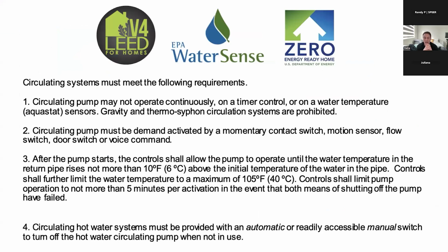In the past, we've seen language as it pertains to hot water recirculation often be pretty ambiguous, right, and open to interpretation. This is not. It says that the circulating pump may not operate continuously on a timer or on water temperature, and gravity or thermosiphon circulation systems are prohibited, and that the pump needs to be demand activated by a momentary contact switch, motion sensor, flow switch, door switch, or voice command. And then after the pump starts, the control shall allow the pump to operate until the water temperature in the return line rises not more than about 10 degrees Fahrenheit or a maximum of 105 degrees Fahrenheit.